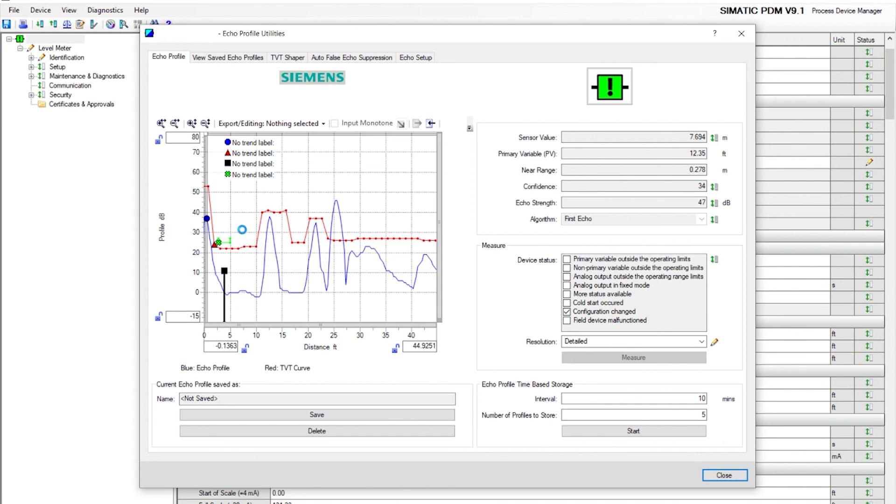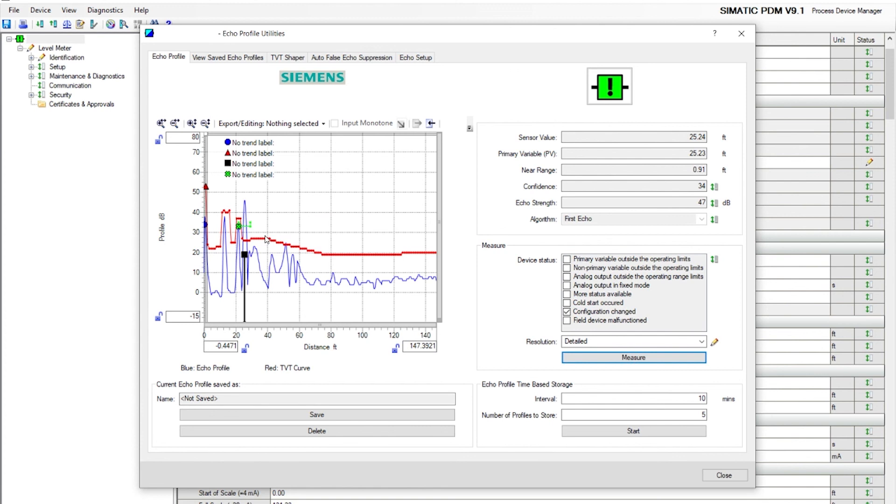As you can see, the red TVT curve in the example that we used, we raised it up above the first echo and the second echo. Now your echo marker is selected on the third echo. That's how you use manual TVT shaper.